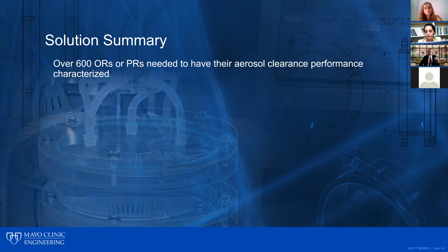So we had over 600 operating rooms and procedure rooms that we needed to test, to characterize their aerosol clearance performance, so we knew exactly how they performed. So we had to develop a methodology. We started by determining the room's baseline aerosol clearance capability. So we measured that for the room. Then we introduced a challenge aerosol and monitored that aerosol concentration over time, and looked at how fast the room ventilation would clear the aerosol. And then we used that to calculate the new room aerosol clearance time.